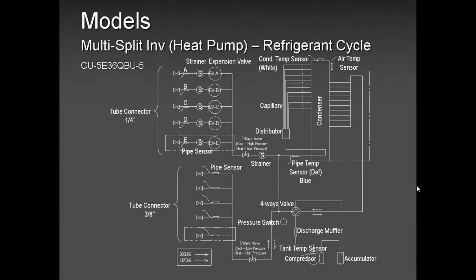That's your refrigerant cycle. I don't think you can see it well because it's very tiny to accommodate all the 5 zones. But bottom line is, these are the indoor units, and that's your outdoor unit section. Every indoor unit will hook up to A, B, C respectively. The biggest problem I have had from the day multi-zones were introduced, like 20 years ago, is cross wiring. And I still have that problem.